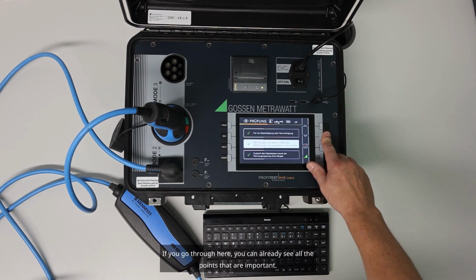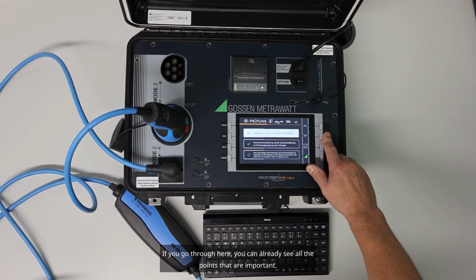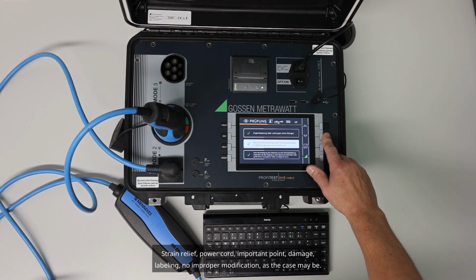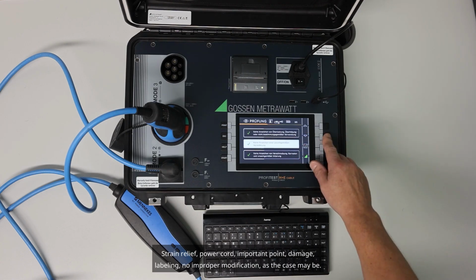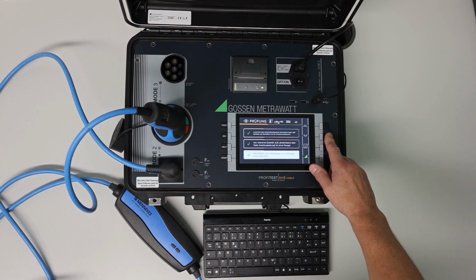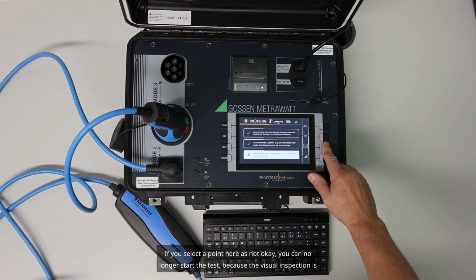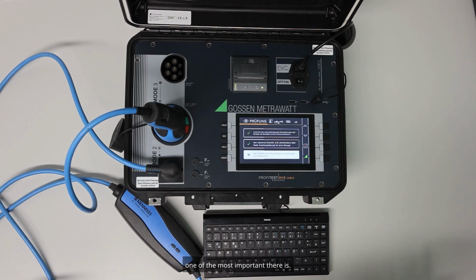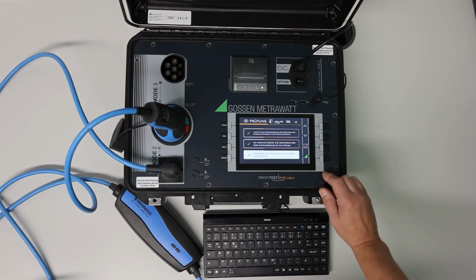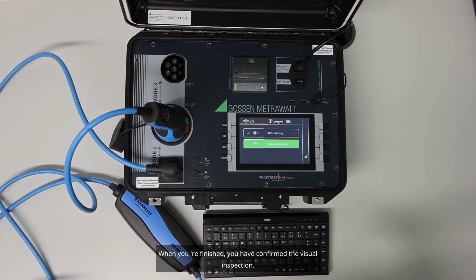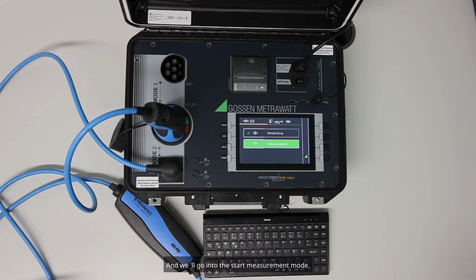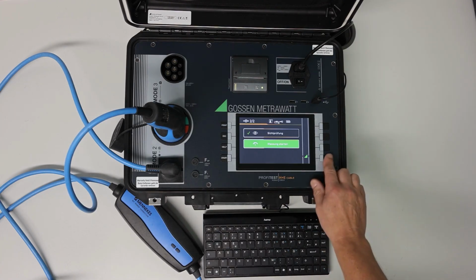If you go through here, you can already see all the points that are important. Strain relief, power cord, important point, damage, labeling, no improper modification, as the case may be. If you select a point here as not okay, you can no longer start the test because the visual inspection is one of the most important there is. When you're finished, you have confirmed the visual inspection and we'll go into the start measurement mode.